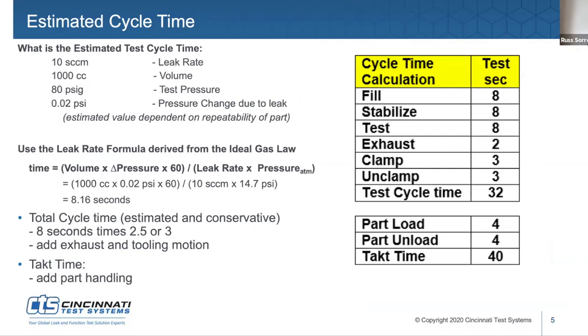Well, let's talk about cycle time. So to determine all that, cycle time, especially in leak testing, we're working with physics. The physics side of it is the ideal gas law. And we use the ideal gas law derived down to what we call the leak rate formula. And we can identify time knowing the volume of a part, the volume of test line, and the volume of the pneumatic manifold of the test circuit.